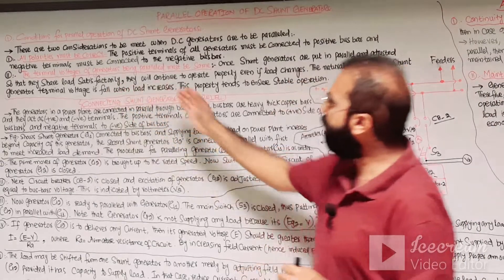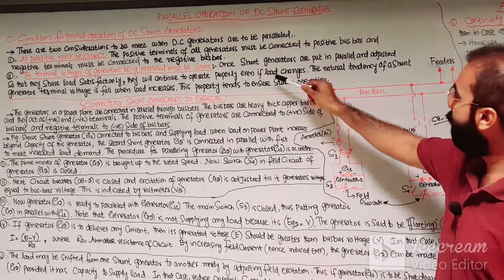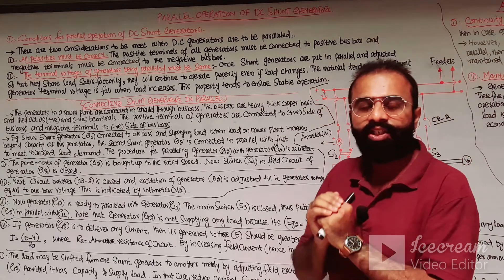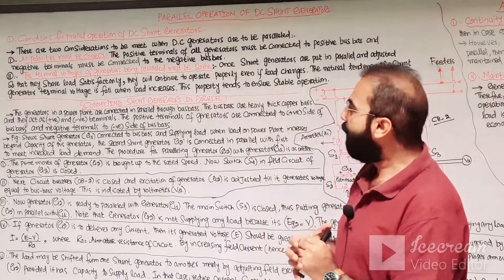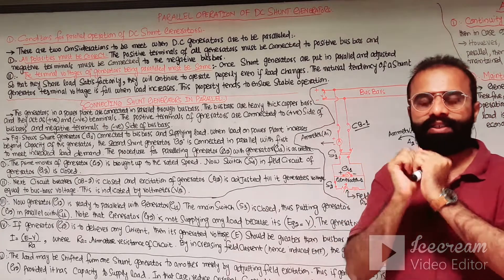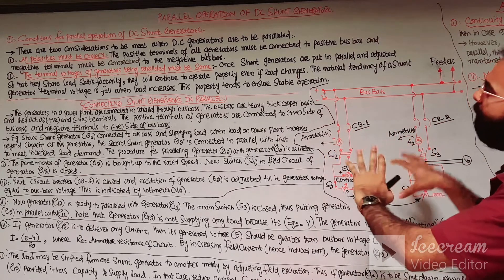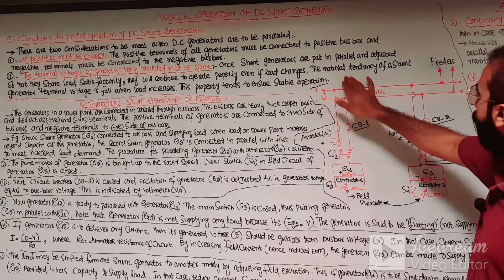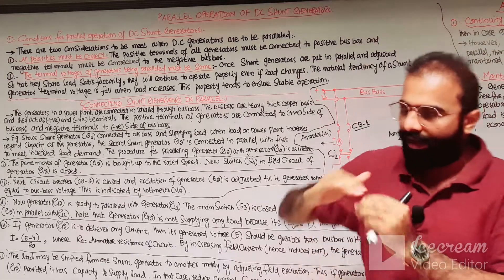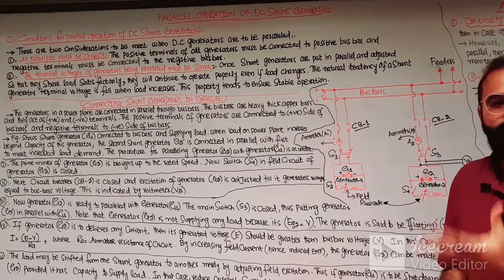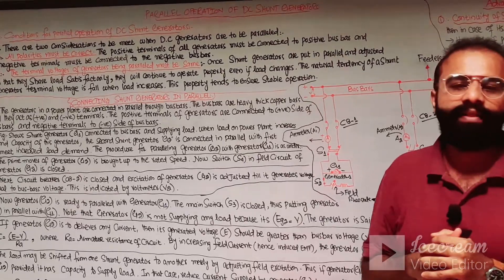The second condition is that the terminal voltages of the generators being paralleled must be the same. Once shunt generators are put in parallel with the bus bar and adjusted so that they can share the load satisfactorily, they will continue to operate properly even if the load changes. The natural tendency of the DC shunt generator is that when the load is increased, its terminal voltage and speed fall.